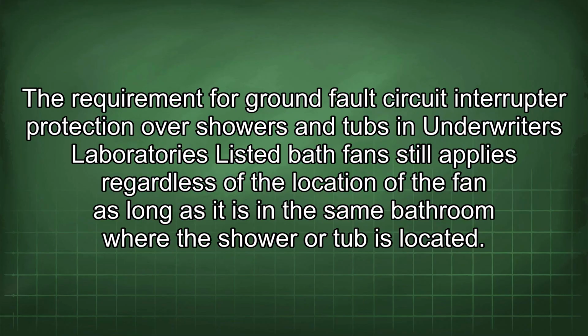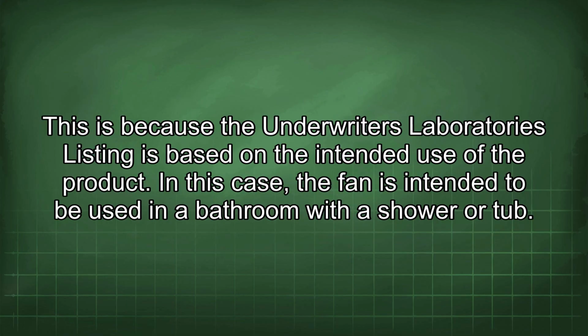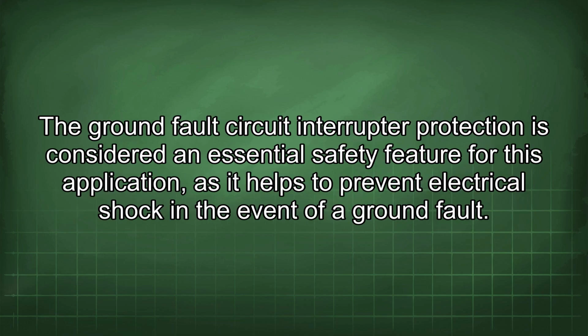The requirement for ground fault circuit interrupter protection over showers and tubs in an Underwriters Laboratories listed bath fan still applies regardless of the location of the fan, as long as it is in the same bathroom where the shower or tub is located. This is because the Underwriters Laboratories listing is based on the intended use of the product. In this case, the fan is intended to be used in a bathroom with a shower or tub. The ground fault circuit interrupter protection is considered an essential safety feature for this application, as it helps to prevent electrical shock in the event of a ground fault.